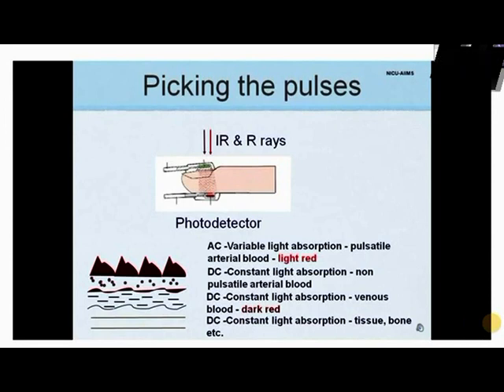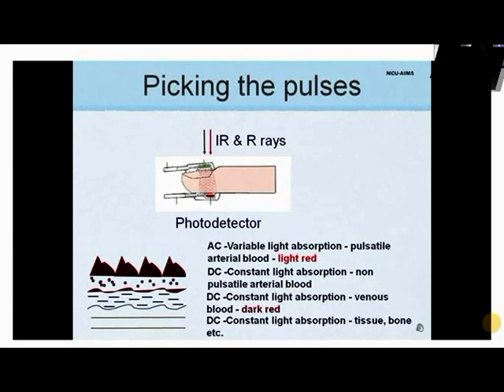Scatter, reflection, and absorbance of light by other tissues and blood components could confound the values. This is solved by the pulsatile nature of arterial blood, which increases the path length, thereby increasing the absorbance. Other tissues, being static, do not contribute to the reading.